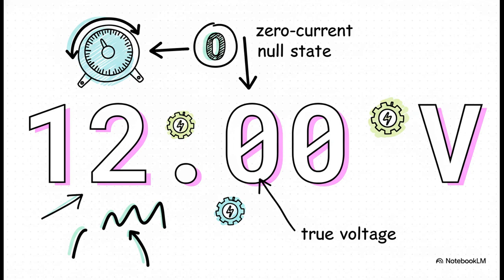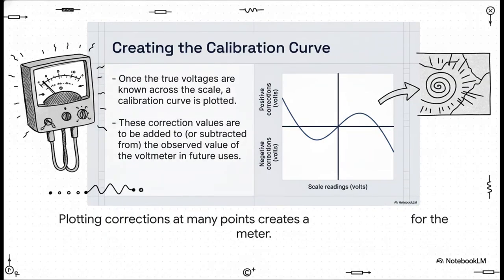That right there is the power of this method. And this brings us to the final goal. We don't just test one voltage. We check a bunch of points all across the meter's scale, and we plot the errors we find. What this gives us is a calibration curve. It's like a unique correction map just for that one specific instrument.